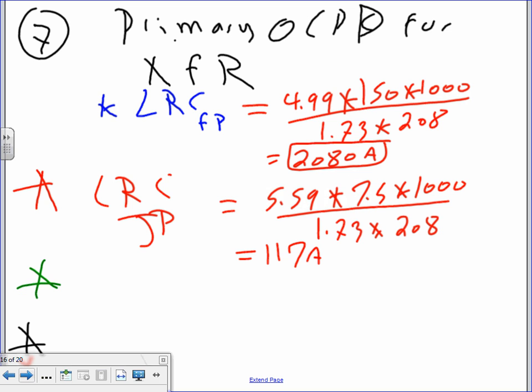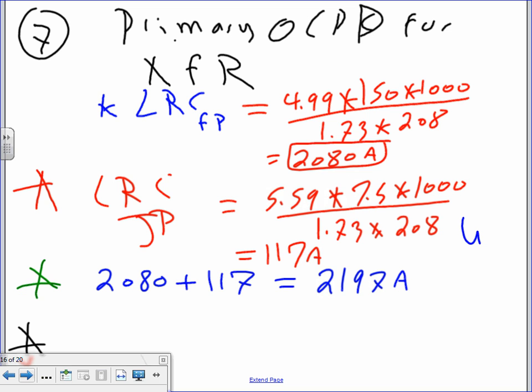The next step is to add them up. 2080 plus 117, like the calculation will tell you, and you end up with 2197 amps. Okay? Any comments, guys, up to this point? Now remember, this is on the 208 side. If you look where the transformer is, here's my transformer. All the calculation that I did is right here, but my overcurrent protection device is right on the 480 side. Here's my 480, here's my 208.